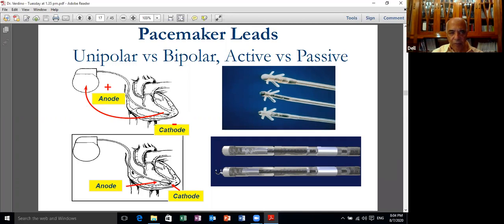And because this is a large window, it senses many of the structures in between, including pectoral muscle activity and so forth. And because of the large span of this window, it has a prominent spike. So the spike is clearly seen, and oversensing is common. This is in contrast to bipolar pacing, which is more frequently used nowadays, in which the cathode is located at the end, and just a few millimeters proximal to it is the anode, and the electrons pass between the cathode and the anode. It has nothing to do with the pacemaker can. It's more complicated, but it allows the display of a small, short pacing spike, and there is no oversensing from external activity. Now, the pacemaker leads are usually fixed either by active fixation, like this tiny screw which is present here.